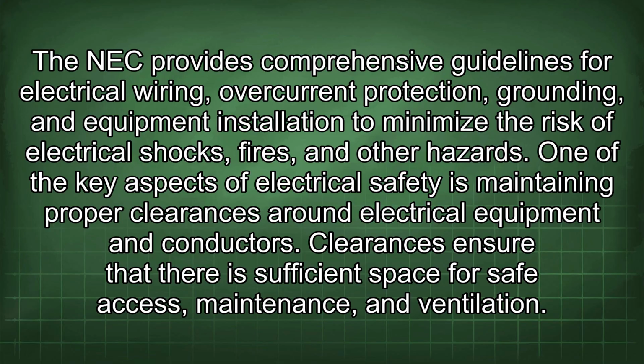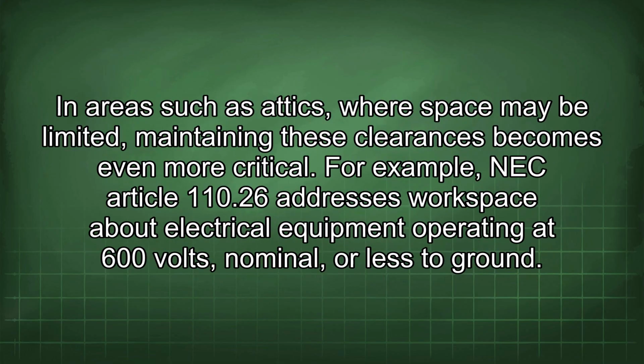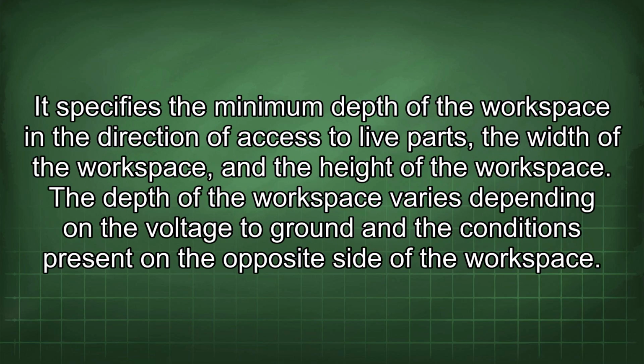One of the key aspects of electrical safety is maintaining proper clearances around electrical equipment and conductors. Clearances ensure that there is sufficient space for safe access, maintenance, and ventilation. In areas such as attics, where space may be limited, maintaining these clearances becomes even more critical. For example, NEC Article 110.26 addresses workspace about electrical equipment operating at 600 volts, nominal, or less to ground. It specifies the minimum depth of the workspace in the direction of access to live parts, the width of the workspace, and the height of the workspace.